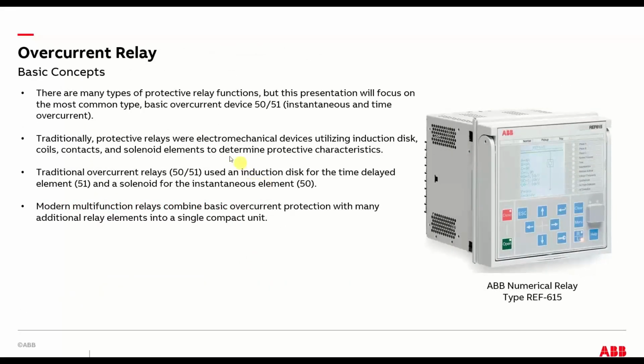Now we're finally getting to the overcurrent relays. Basically, I'm just going to go through. There's many types of relays that do all kinds of different protection functions, but I'm keeping it really simple. It's just an overcurrent device. And so this would be your 50, 51, 50 being instantaneous, and 51 being your time overcurrent. Here's an example of, again, the same multifunction relay, but in the next couple slides, I'm going to start out with the electromechanical and then move my way up into numerical.